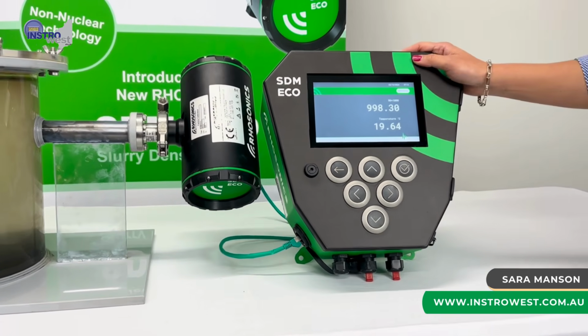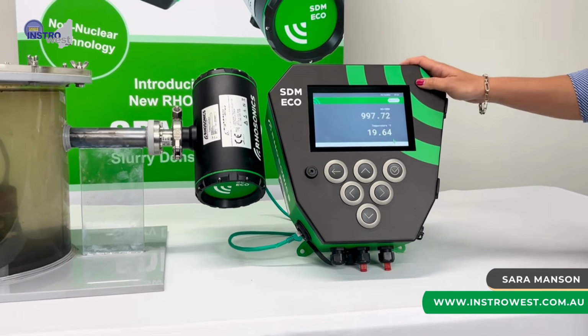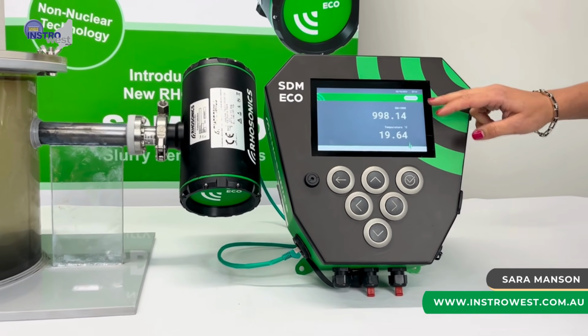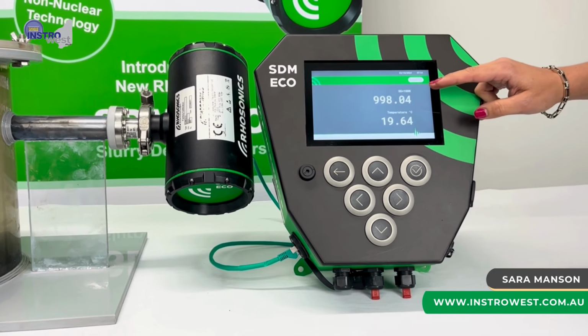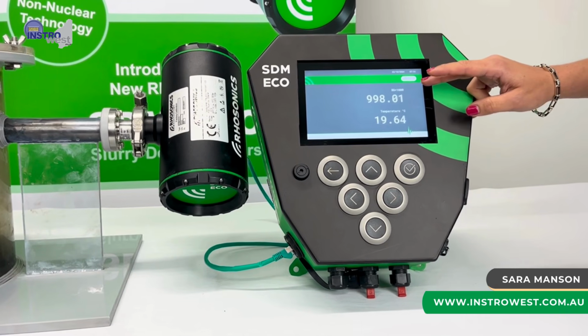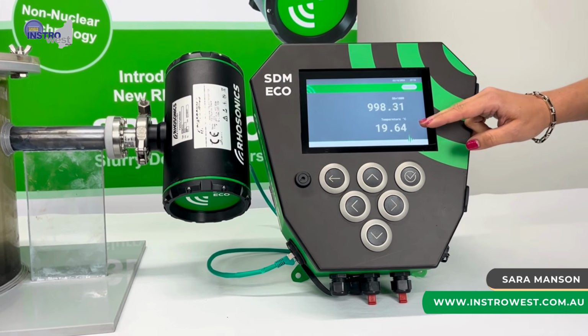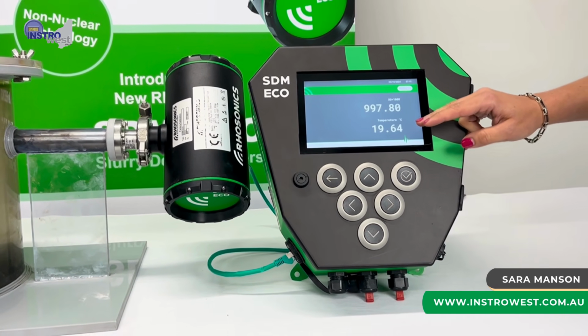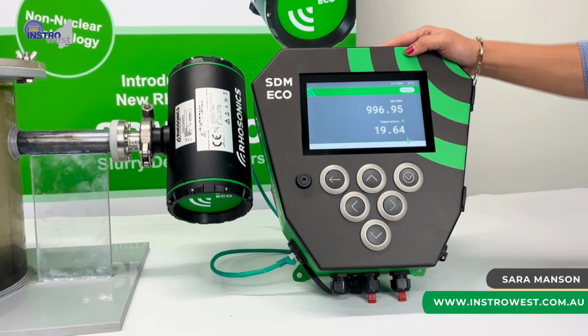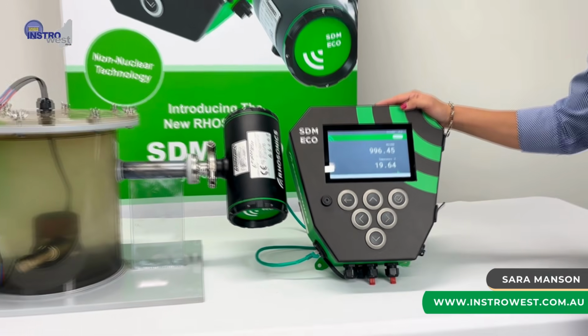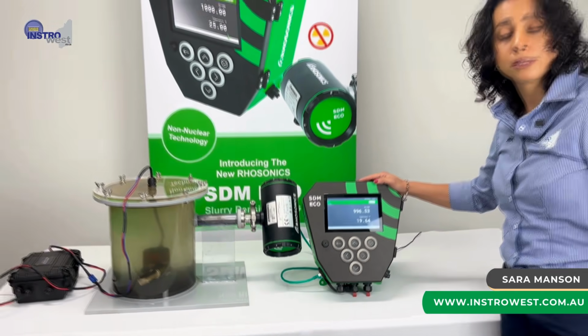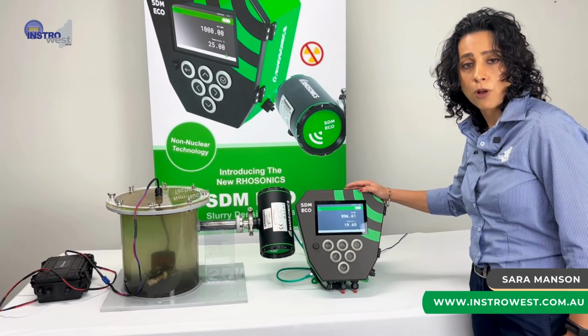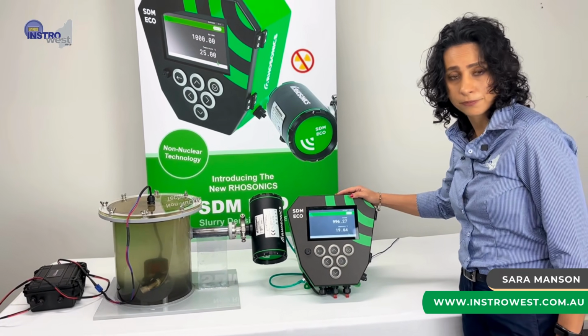Now let's have a look at the screen. You have two readings. On top is density in kilogram per cubic meter or SG in 1000. And on bottom you have temperature in degrees centigrade. SDM ECO constantly measures temperature. It compensates for temperature to provide more accurate results.